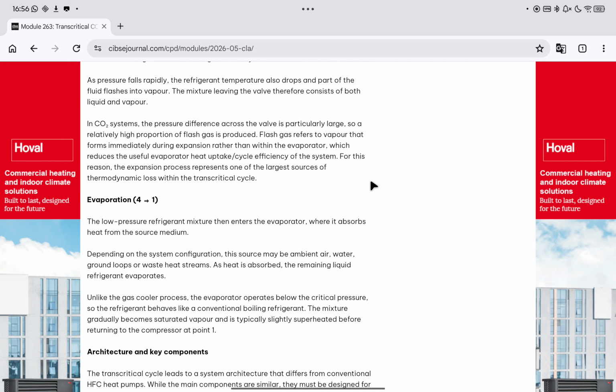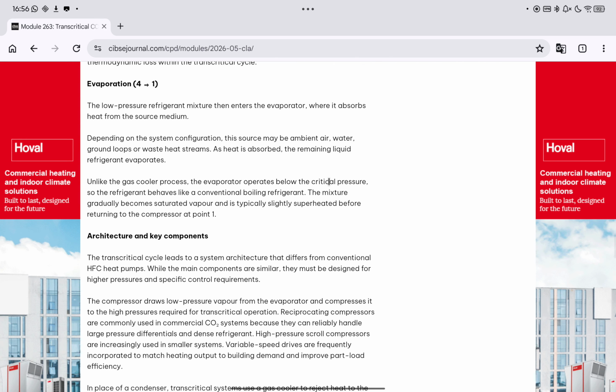Evaporation. The low-pressure refrigerant mixture then enters the evaporator, where it absorbs heat from the source medium. Depending on the system configuration, this source may be ambient air, water, ground loops, or waste heat streams. As heat is absorbed, the remaining liquid refrigerant evaporates. Unlike the gas cooler process, the evaporator operates below the critical pressure, so the refrigerant behaves like a conventional boiling refrigerant. The mixture gradually becomes saturated vapor and is typically slightly superheated before returning to the compressor at point 1.